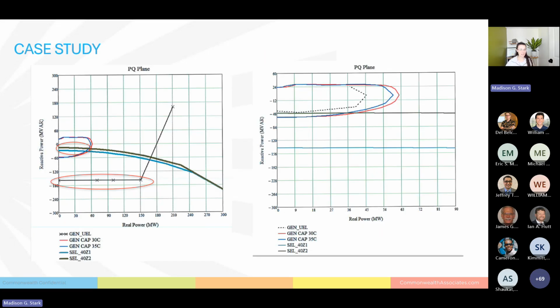So this is a quick case study. These were just default settings that we saw on one, and how to properly coordinate them. I highlighted in red the parts that are like, maybe this isn't exactly what we're looking for. The biggest thing is, one, we have these two relays all the way inside the generator capabilities. So these are going to kick the generator offline when it does not need to be kicked offline. So we're going to lose power for no reason. Not what we're looking for with PRC 19. And then this limiter down here, which we're really hoping would be used to curtail power, is actually not doing anything. The generator is going to burn up far before it hits this under excitation limiter. So not what we're looking for.